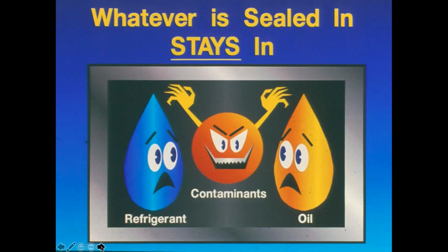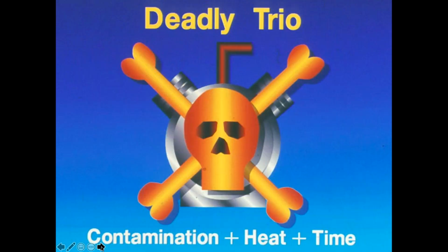These are the only refrigerant and oil. These are the two only good things in any system. Don't have any contaminants in the system. That's why I suggested TIG welding, MIG welding for pipelines, and cleaning of pipelines before they are installed, because they are lying in the dust for a very long time, and all that dust can go inside the machines if you don't clean them. So contamination, heat and time is a deadly trio.